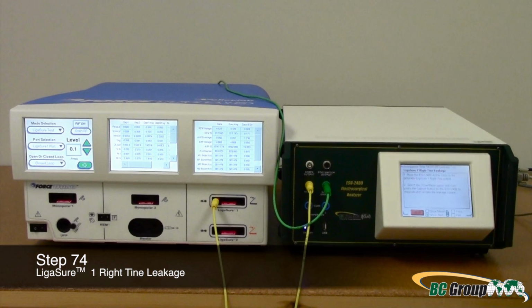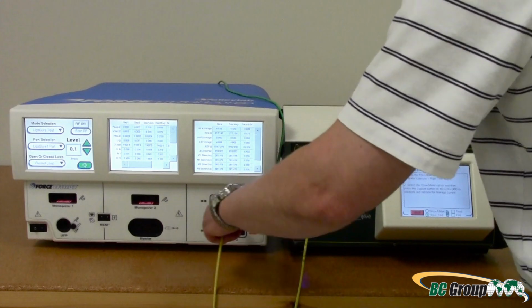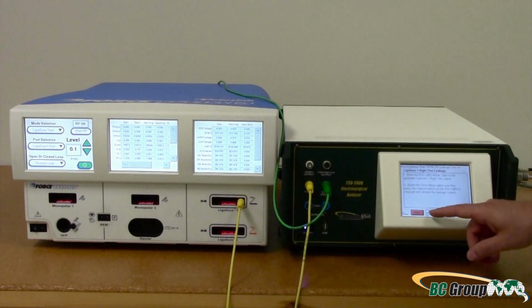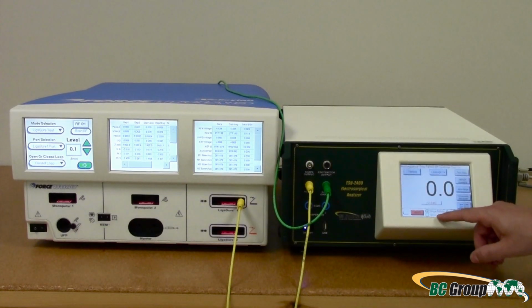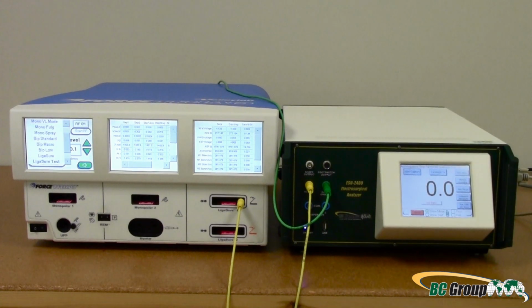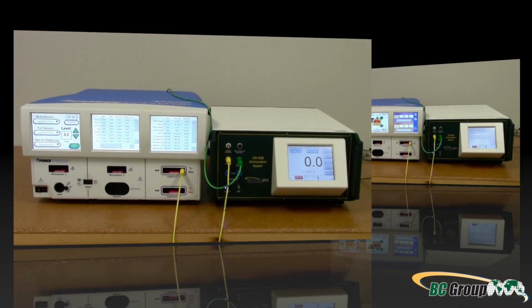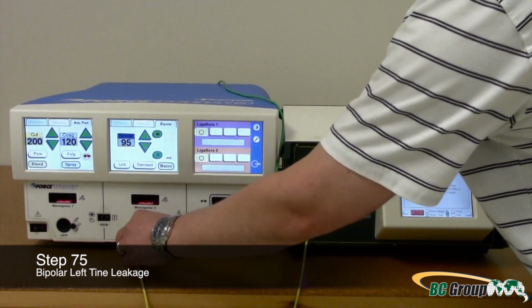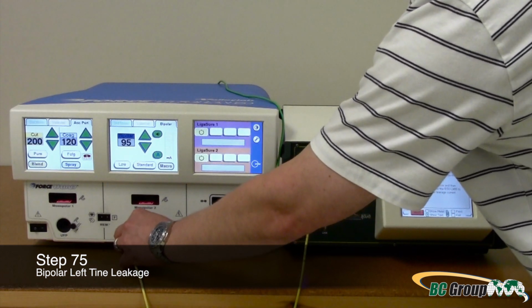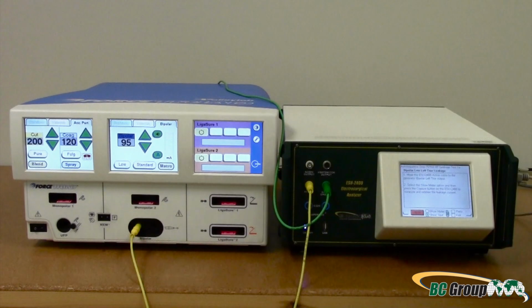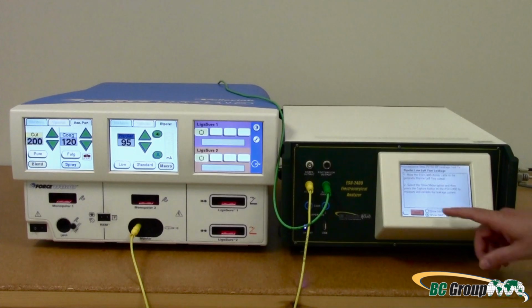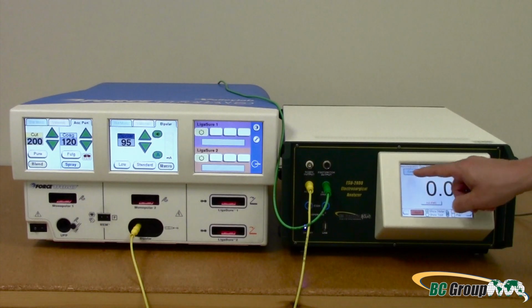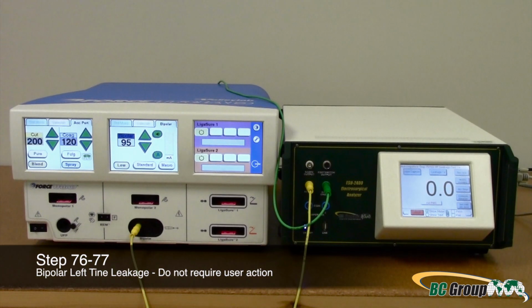Step 74. LigaSure 1 right tine leakage. Move the ESU-2400 active cable to the right tine of the LigaSure 1 port. Select Show Meter and then press Capture. Step 75. Bipolar left tine leakage. Move the ESU-2400 active cable to the left tine of the bipolar port. Select Show Meter and then press Capture. Steps 76 through 77 do not require user action.